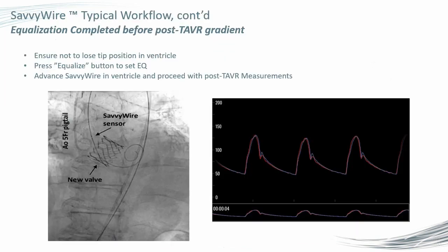Once you've deployed your valve, this is the second part of the workflow. So where previously you would then exchange your workhorse wire, your Amplatz or your Safari or your Confida for a pigtail, flush it, reconnect it, and remeasure gradients, none of that happens anymore. You simply pull the wire back. Remember that dot which represented the transducer? Now you want to pull that back as close to the valve without coming out so that you equalize with your aortic pressure. Once you've equalized on the same system, you simply advance the wire gently forward back into the LV once you've calibrated to get the differential gradient, residual gradient between your aorta and your LV.